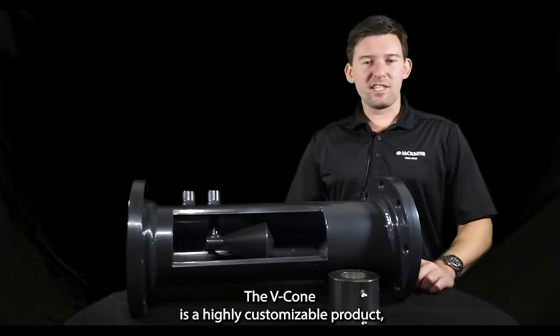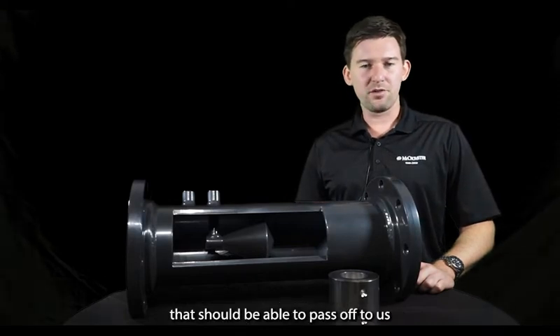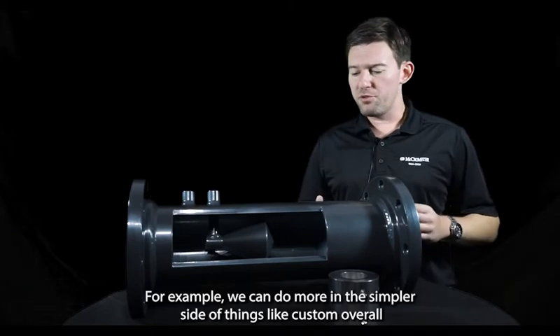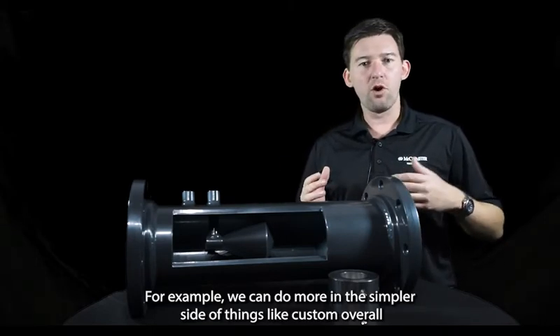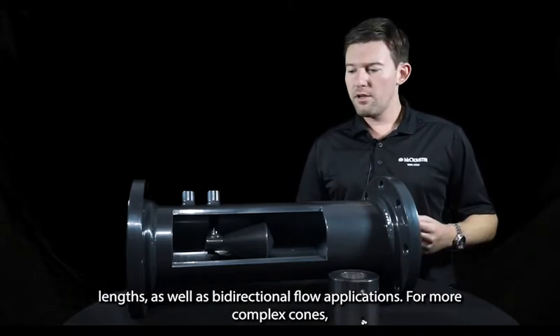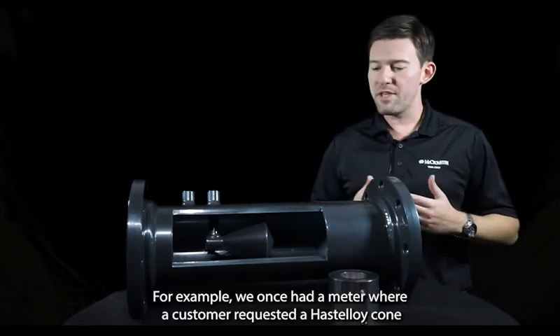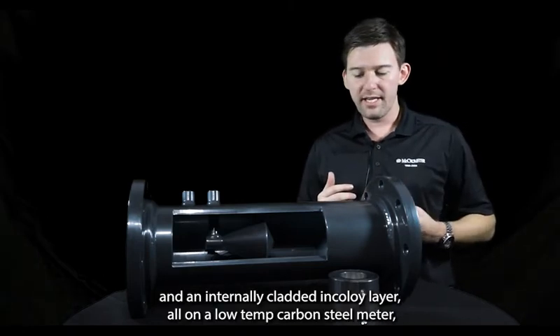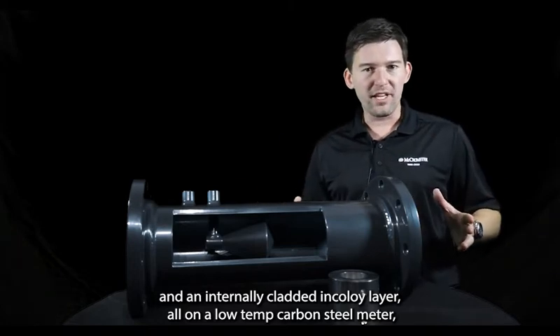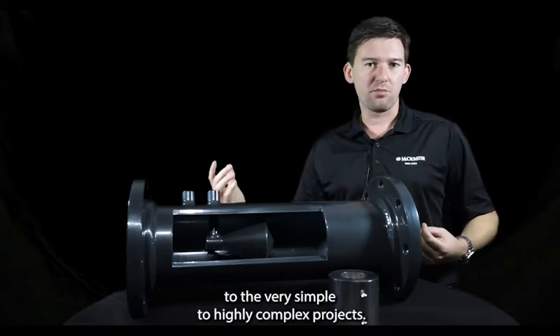The V-Cone is a highly customizable product. Leveraging our engineering assets, we're able to take a set of specifications and create a highly customized cone. On the simpler side, we can do things like custom overall lengths and bi-directional flow applications. For more complex cones, we can look at higher levels of material specification — for example, we once built a meter with a Hastelloy cone and an internally clad Incoloy layer, all on a low-temp carbon steel meter, which was then painted. So we can go from very simple to highly complex projects.